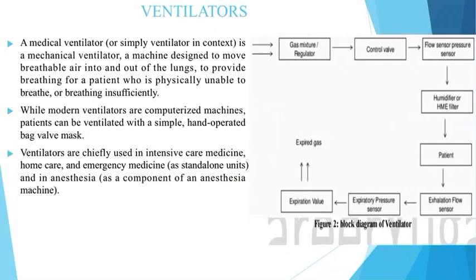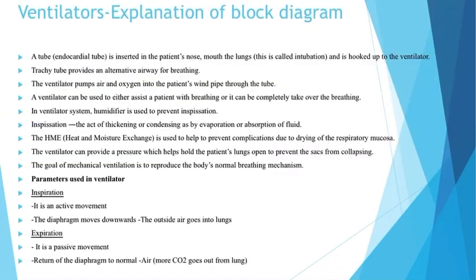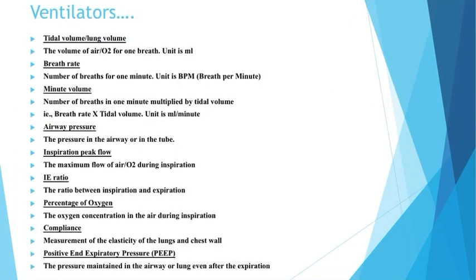Now let's see the various parameters used in ventilators. The first one is inspiration — the intake of oxygen. During this process the diaphragm moves downwards and this process is an active process. The second parameter is expiration — the expelling of carbon dioxide from the lungs. During this process the diaphragm moves upwards, and this process is a passive process. The next parameter is tidal volume or lung volume, which refers to the volume of air or oxygen for one breath and is measured in milliliters.